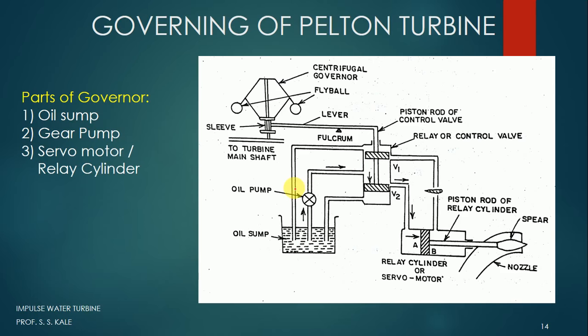The next part is the servo motor or relay cylinder, which is the total cylinder-piston arrangement. In this arrangement there is a piston and a piston rod, called the piston rod of the relay cylinder. This piston rod is connected to a spear, which is inserted into the nozzle. From the nozzle, water goes to the turbine. Basically, controlling the speed of the Pelton turbine means controlling the amount of water going to the turbine. If you reduce the water going to the turbine, the rotation reduces; if you increase it, the rotation increases.